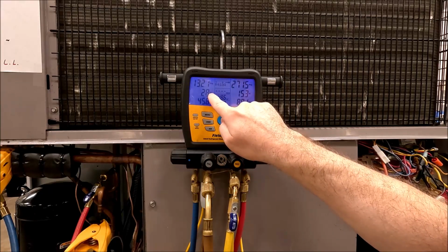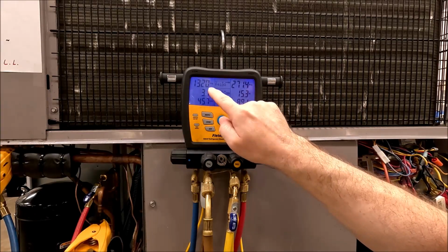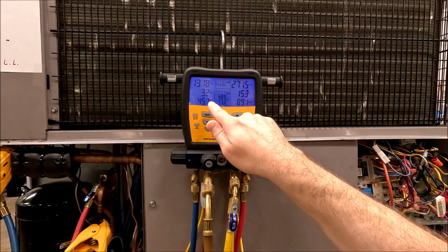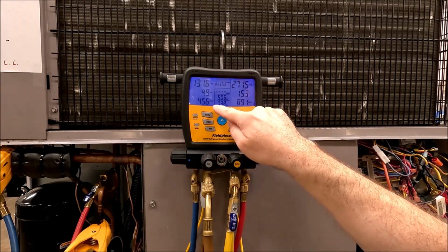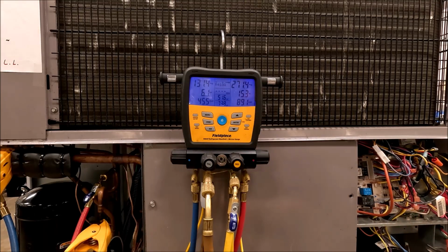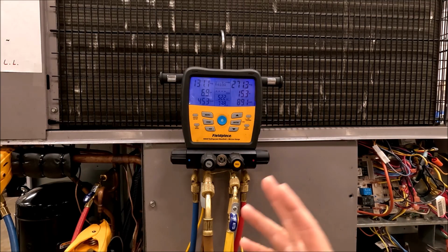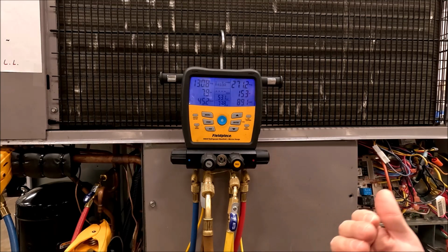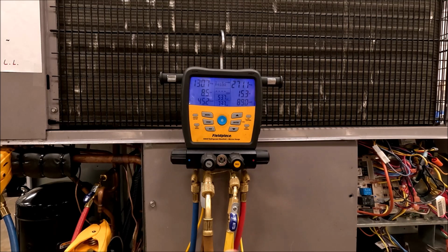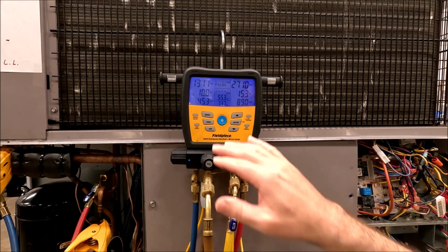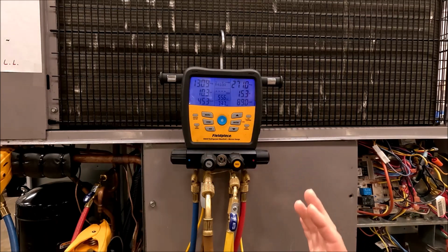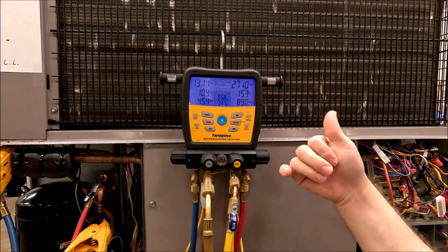So this superheat, it doesn't tell you the vapor line pipe temperature. It tells you the saturation point for the given pressure. But wherever you clamp that pipe clamp, right or wrong, it's gonna do math. And it knows that the numbers it should be working with is a vapor line temperature on the low side going from the evaporator to the compressor, that number better be higher than the saturation point, okay? If it's not, you don't get a superheat reading. Superheat does not go negative. It's either 0 or a positive value.